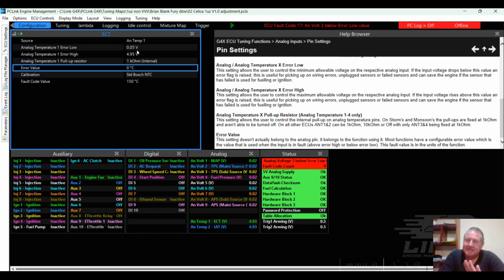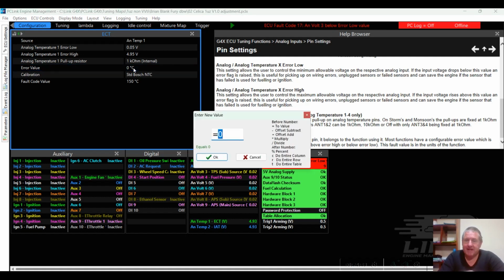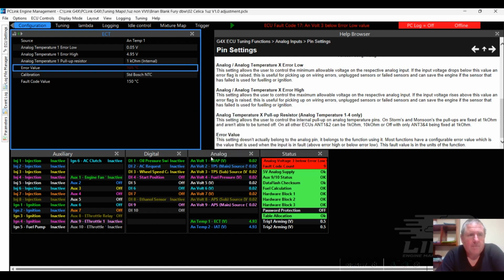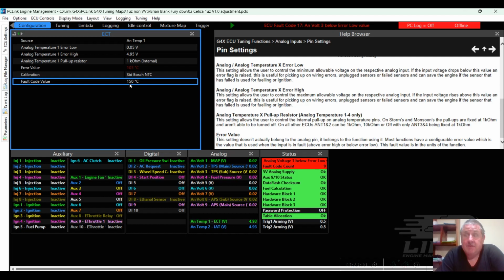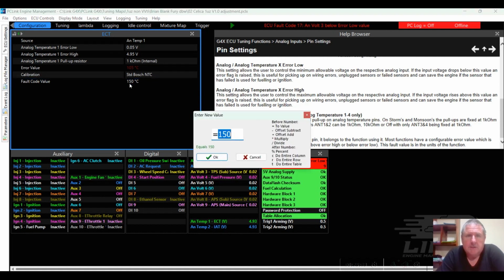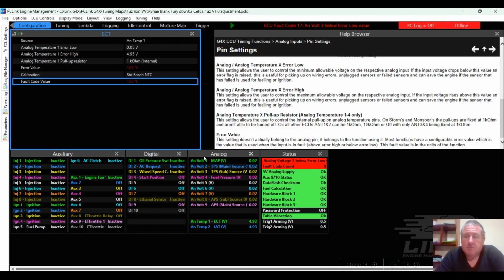Again, they should be tightened up once you get that thing running. And we're going to chuck in an error value of fans plus a little bit more, 105. 105. And if it hits 150 degrees, you've really got a problem. Error value, I'm going to put an error value a little bit lower, 125. You can probably bring that down. So again, it'll bring a fault code up. It'll bring a fault for that sensor if it gets over 125 degrees. If it's reading over 125, it goes, there's a problem.